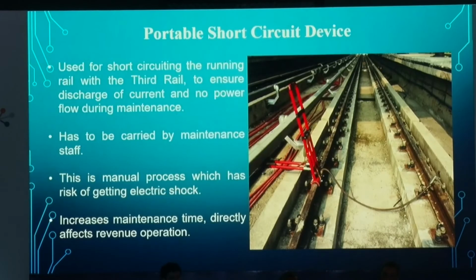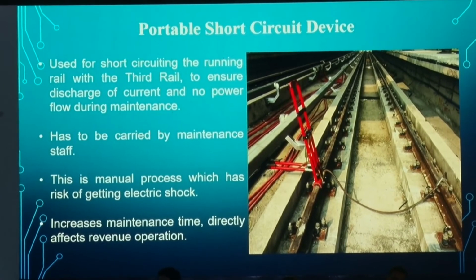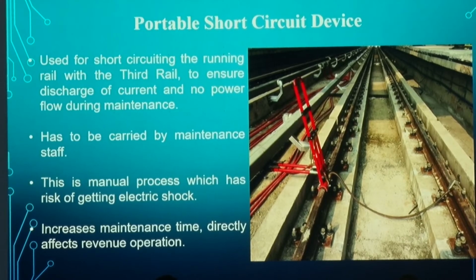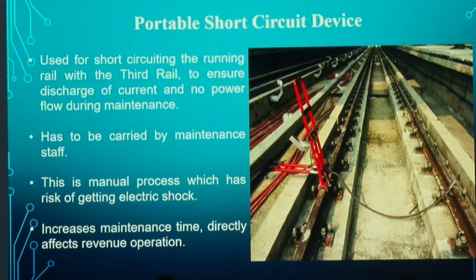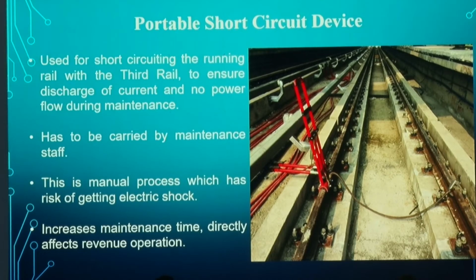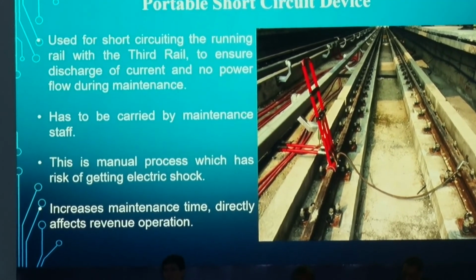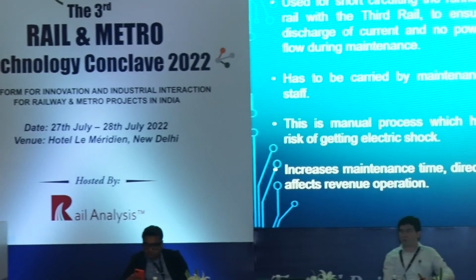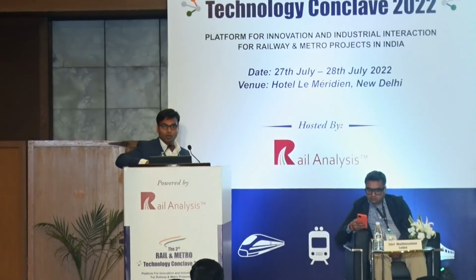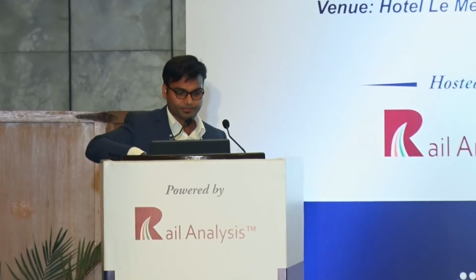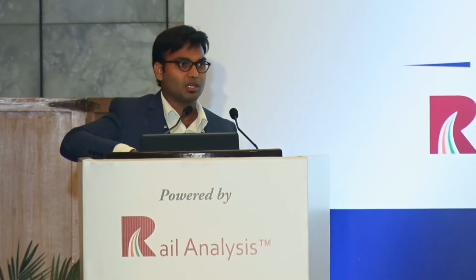Another new thing which we have used in Kanpur Metro is, let's talk about in DC traction system, or for that matter in AC also. Whenever we take a power block for maintenance, we have to use the discharge rods to make sure that there will not be any residual voltage or any residual current, or in case of during maintenance there should not be any power flow. In DC traction system we are using portable short circuiting devices. It's a similar form to what we use in AC traction system. In this we just short both the running rails and the third rail to discharge all the residual voltage. This discharge rod is a bulky device, around 25 kg or so, and this has to be carried out by the maintenance staff.